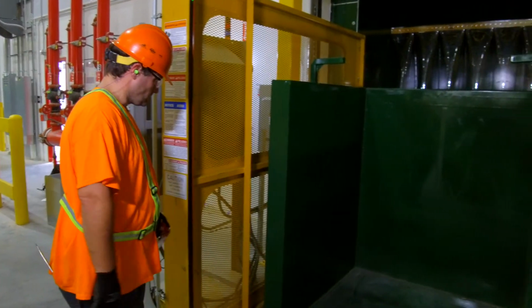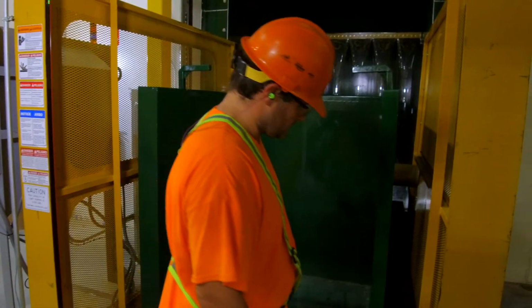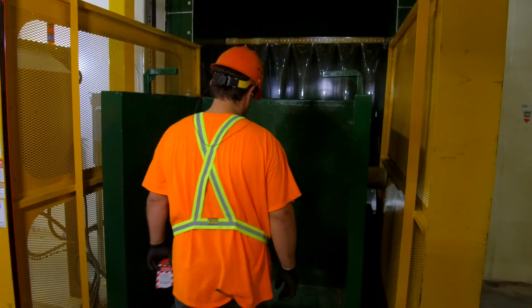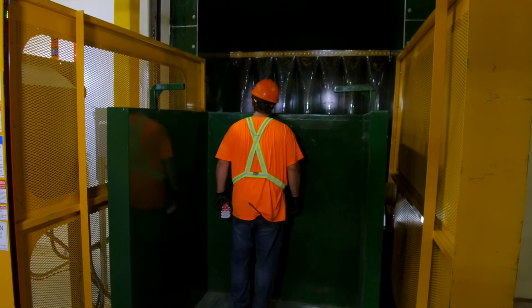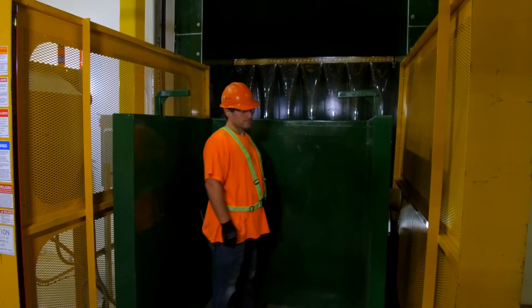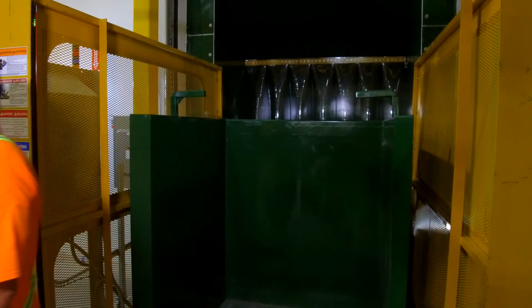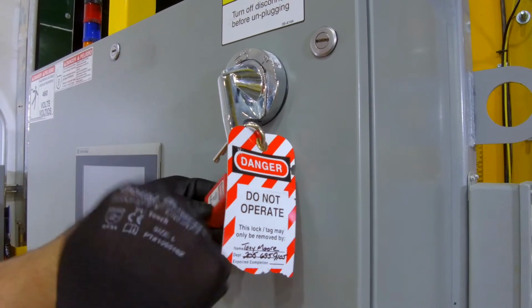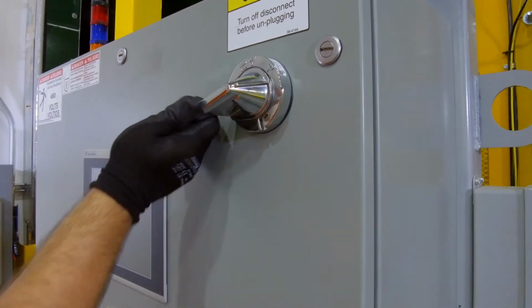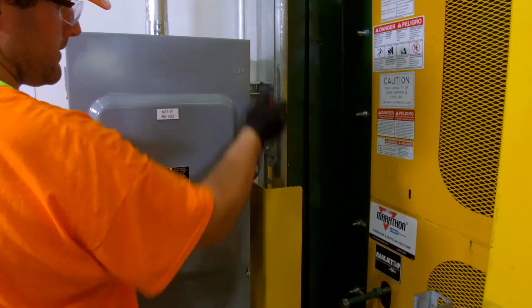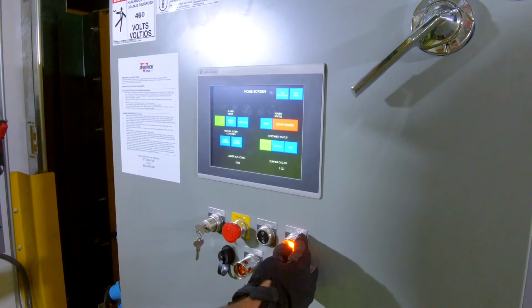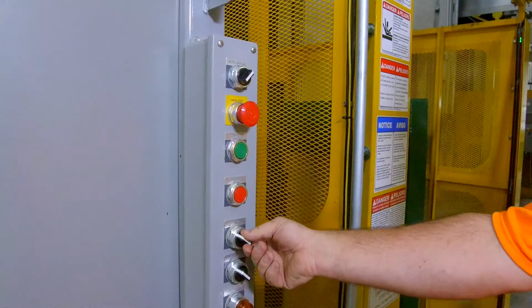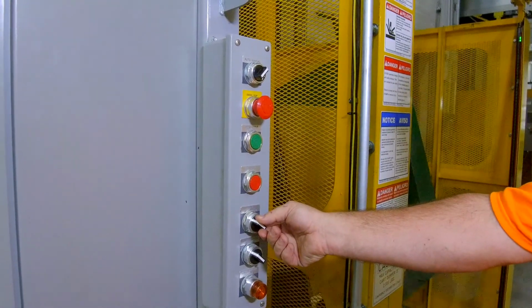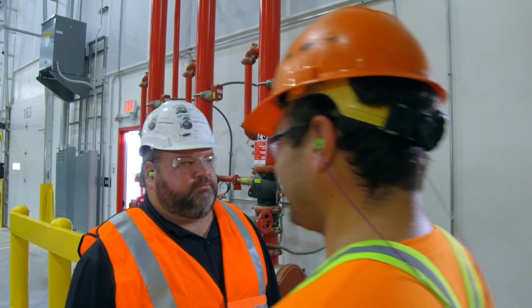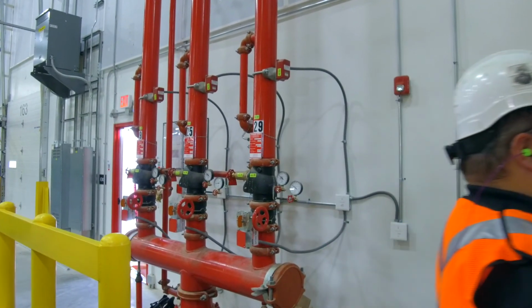After completing maintenance, you will need to remove the system from the lockout tagout. First, check the work area to ensure all employees have been safely positioned or removed from any hazardous area. Remove the system from lockout tagout and move the disconnect lever back to the on position. And check that all of the functions are operating correctly. Finally, notify affected employees that the servicing or maintenance is completed and that the system is ready for use.